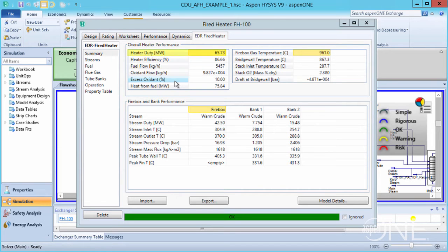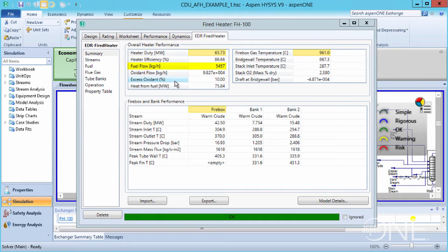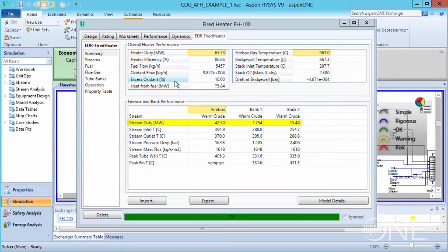In this tab, you can see that the heater duty is 65.73 megawatts. The efficiency is 86.66, and we need 5,457 kilograms per hour of fuel to achieve our required outlet conditions for the crude. You can see the split in duty between the firebox and the convection bank, and we can see the peak tube temperature calculated for the firebox and in the convection sections.